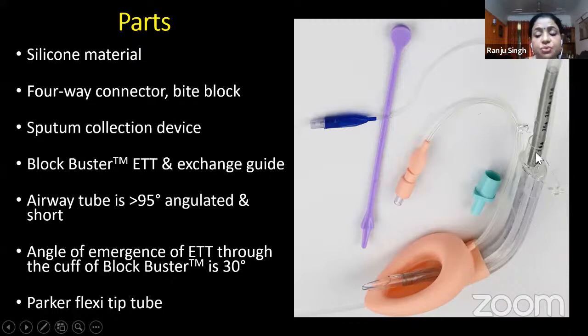Many of the previous devices which were used for endotracheal intubation had longer airway tubes. If you've seen the Protector and the LMA Blockbuster, the airway stem is much shorter, which allows more successful endotracheal intubation. If the stem is long, when you pass the endotracheal tube through it, it tends to get lost. In this, the stem is smaller. Also, this device is available, which is meant to push the tube in and then remove the tube over this device, which is the exchange guide.